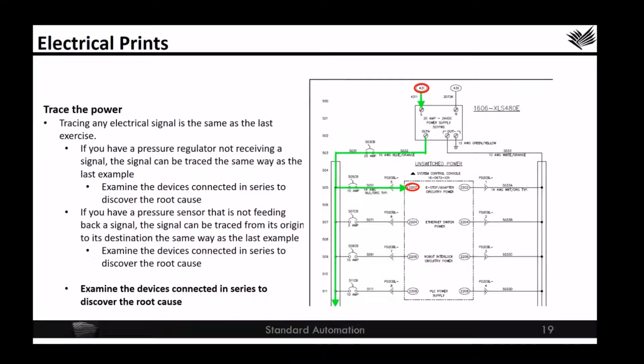If you have a pressure regulator that's not receiving a signal, then the signal can be traced the same way as the last example. The way that you do that is examine the devices connected in series to discover the root cause. If you have a pressure sensor that is not feeding back a signal, the signal can be traced from its origin to the destination the same way. Examine the devices connected in series to discover the root cause. So if you're troubleshooting with the electrical prints package, the main rule is to examine the devices connected in series to discover the root cause. Now, you may find that it's the first device that's not generating the correct signal, or you may find that it's the last device that's not receiving the correct signal, and maybe those devices need to be replaced. But you figure that out by examining the devices connected in series to discover the root cause.